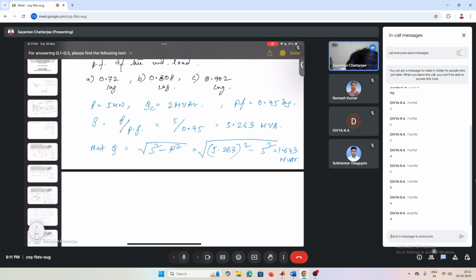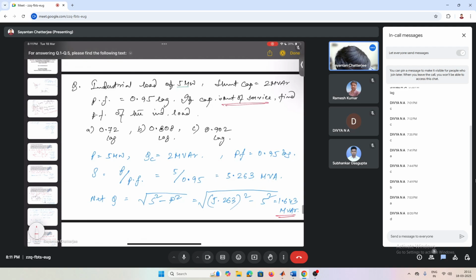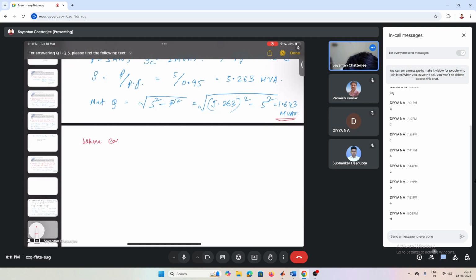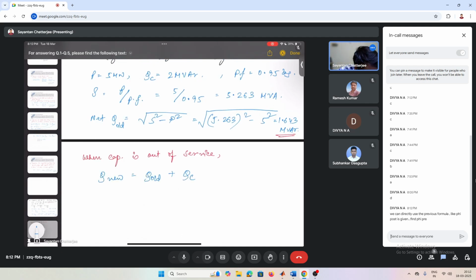So this is when the capacitor is connected. Now the capacitor becomes out of service. So when capacitor is out of service, then Q new would be Q old plus QC, since QC now becomes the total capacitive power that is required to be delivered from the source end. So Q new is 1.643 plus 2, which will be 3.643 MVAR.